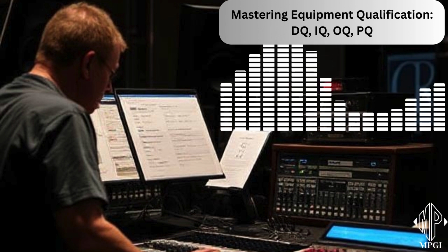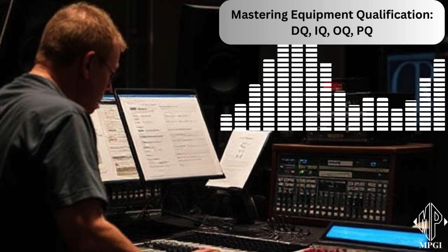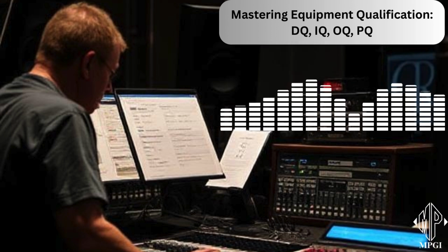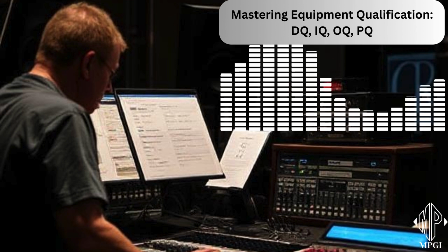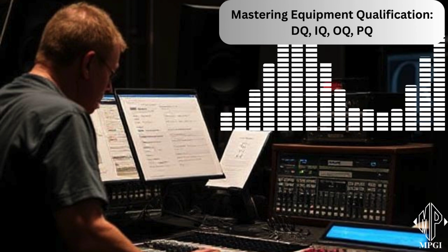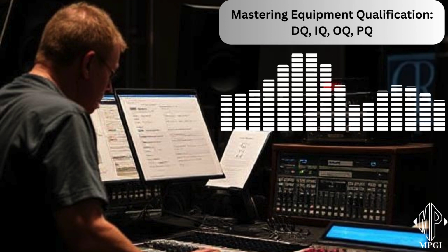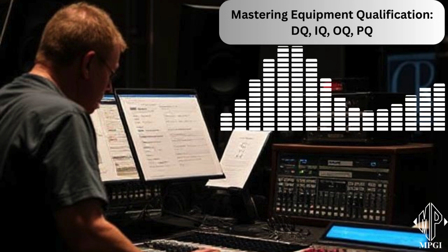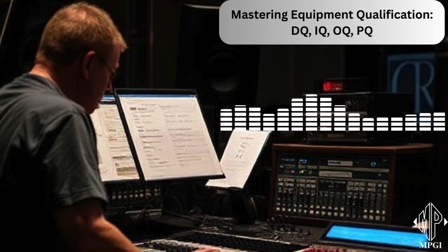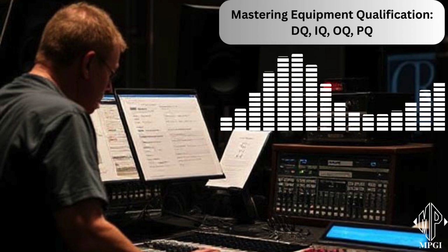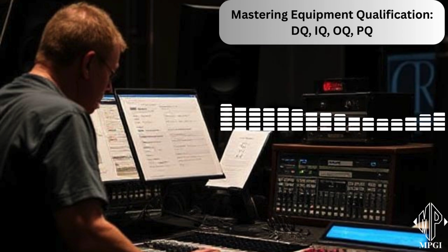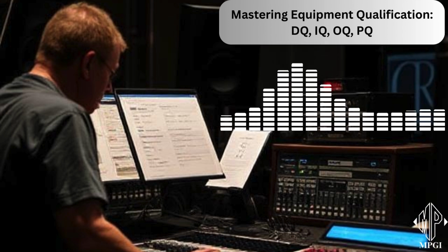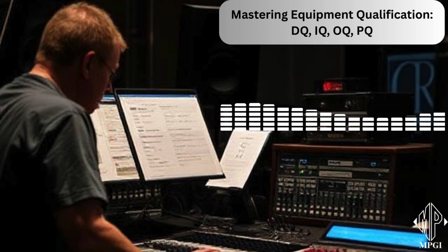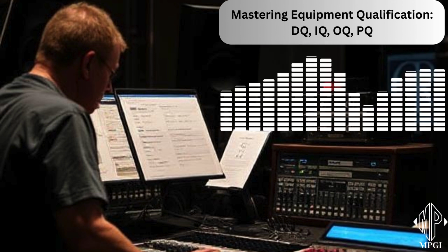Lots of technical terms there, but basically making sure the HPLC is working properly and giving accurate results. Right. And OQ applies to all kinds of systems, like clean rooms, where they check things like airflow and particle counts, or software, where they look at functionality and data security. Mhm. Even utility systems like compressed air or purified water undergo OQ to ensure they meet the right quality standards. So it's not just about the equipment that directly makes the product, it's about the entire environment and all the supporting systems. Exactly. Everything that can impact the final product quality has to be qualified.